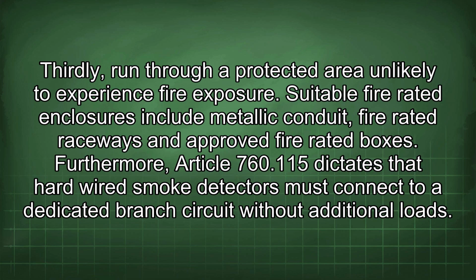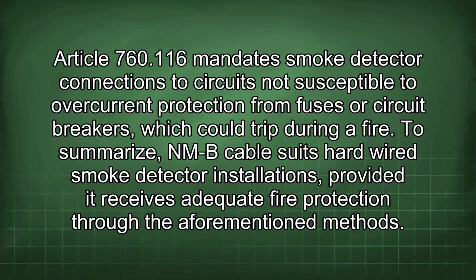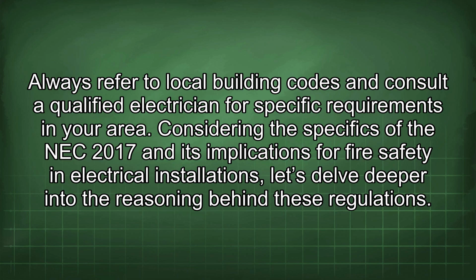Furthermore, Article 760.115 dictates that hardwired smoke detectors must connect to a dedicated branch circuit without additional loads. Article 760.116 mandates smoke detector connections to circuits not susceptible to overcurrent protection from fuses or circuit breakers, which could trip during a fire. To summarize, an NMB cable suits hardwired smoke detector installations provided it receives adequate fire protection through the aforementioned methods. Always refer to local building codes and consult a qualified electrician for specific requirements in your area.